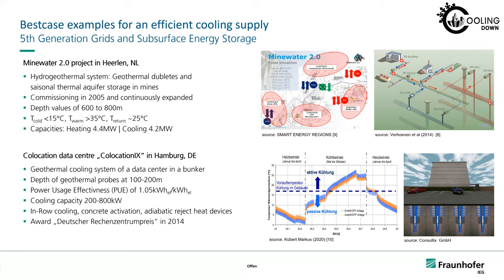Data centers have also been mentioned already. Here's an example of one of the many efficient data centers: the co-location data center in Hamburg, using a geothermal cooling system in a bunker. The geothermal probes go down to 200 meters and provide cooling capacity up to 800 kilowatts. Combined with concrete activation and adiabatic reject heat devices, the power usage effectiveness value - how much electricity is used for providing IT services - is very low, going down to 1.05.